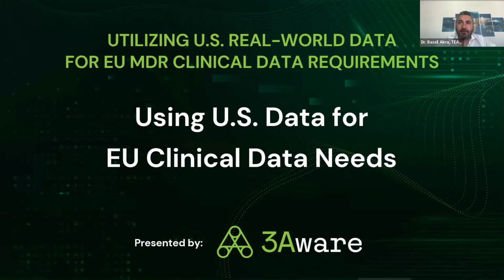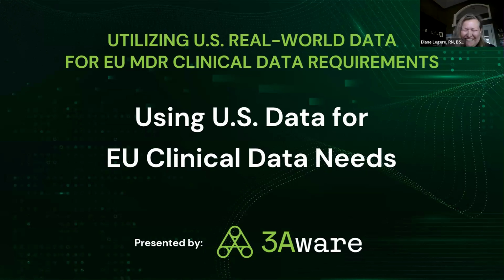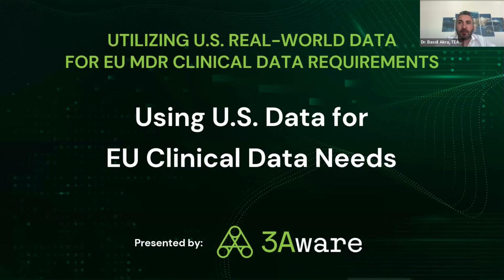I mean, the typical answer that a notified body will always give you is it depends, because it depends on the difference. If we are referring to a device approved in the US for a different indication, it's a different topic to discuss. You are talking about the steps that the physician will apply to introduce a device, and the way they do it might be a bit different. Then you look at whether it impacts the clinical outcome. Some of these differences might be related to usability, but don't impact the safety and performance of the device. But if they are introduced in a way which might impact the data, then the data can be used as supportive, but not the main evidence.